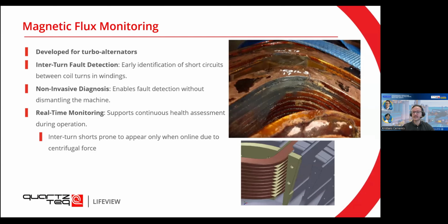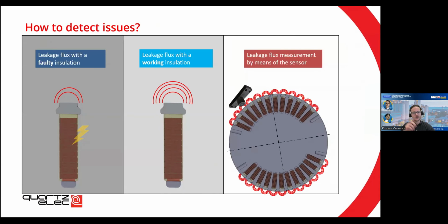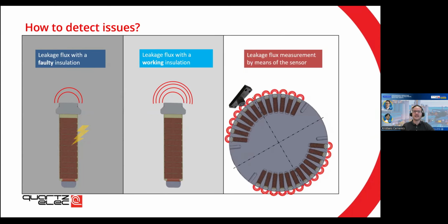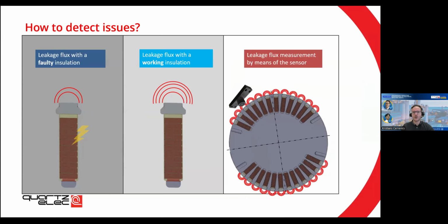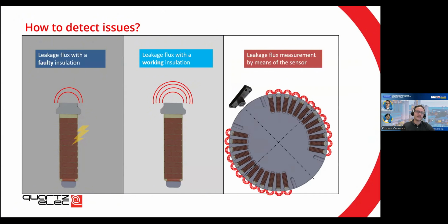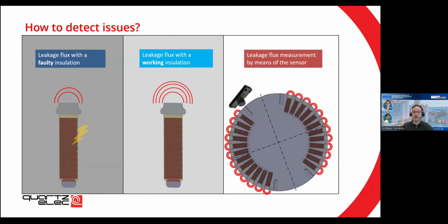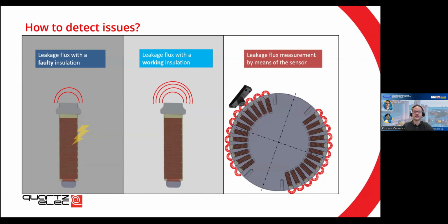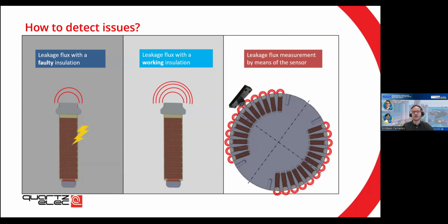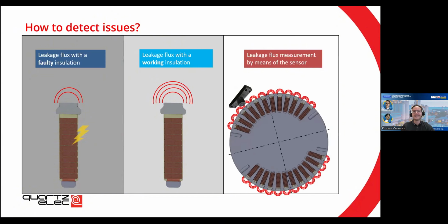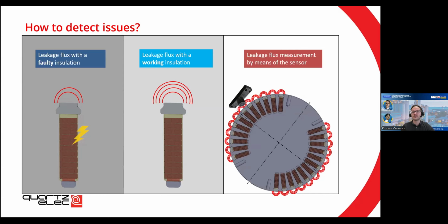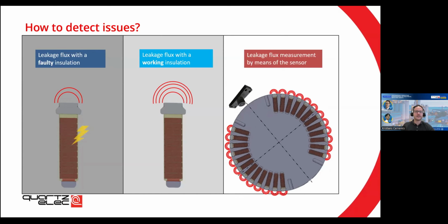For this, what we suggest is that the measurements need to be made online, and the condition should be established online, because it can be that the inter-turn shorts only appear when the machine is on. Once there is centrifugal force, only then some of these issues can appear. So how do we measure magnetic flux? On the right, you can see the rotating machine and a sensor placed on the stator. You have the two poles, and essentially each of the coils goes through the sensor one by one. What we can do is measure the leakage flux, and for working insulation, this will be one value. However, if there is a short, we're going to see less flux going out of the turn. So if you compare two different coils and you can see that one of them is lower than the other one, it is an indication that there is a problem in the insulation, and then most probably there is a short.